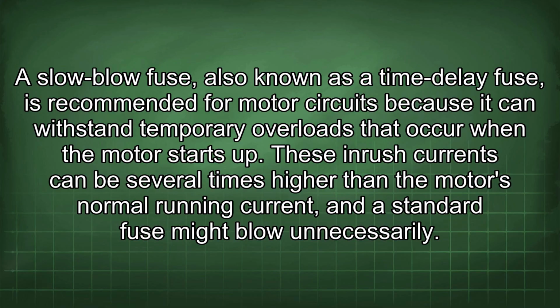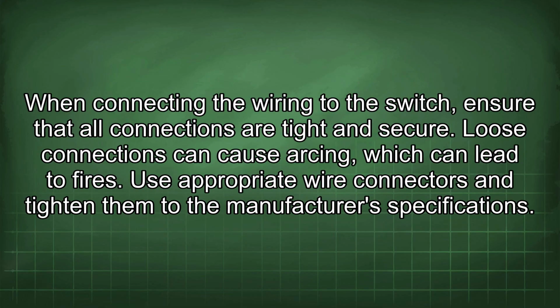A slow blow fuse, also known as a time delay fuse, is recommended for motor circuits because it can withstand temporary overloads that occur when the motor starts up. These inrush currents can be several times higher than the motor's normal running current, and a standard fuse might blow unnecessarily. When connecting the wiring to the switch, ensure that all connections are tight and secure.